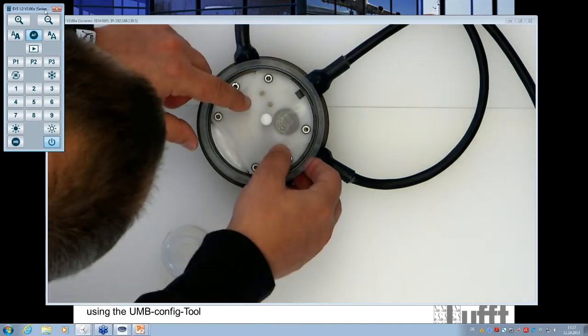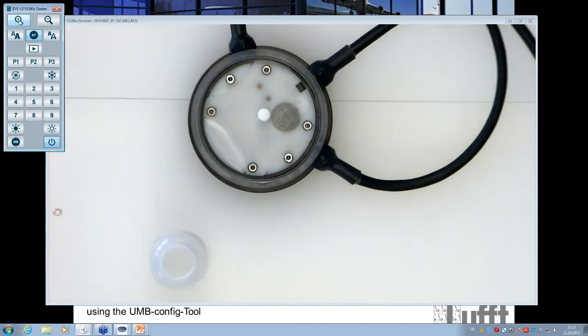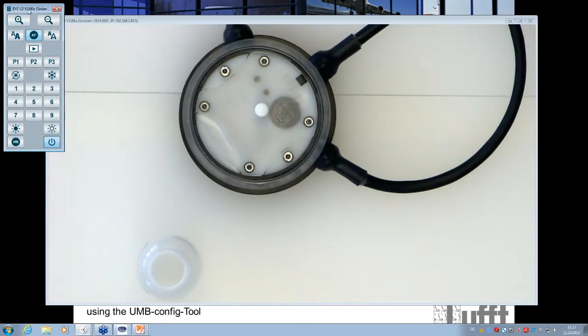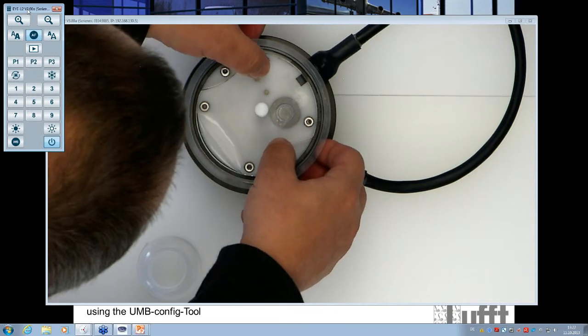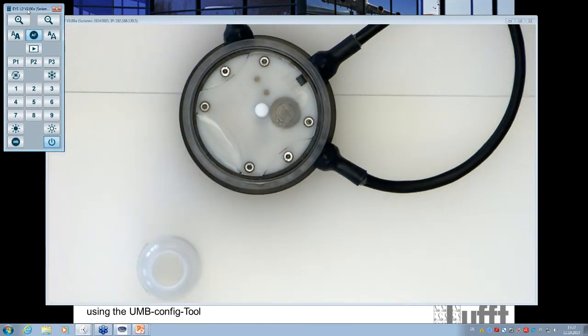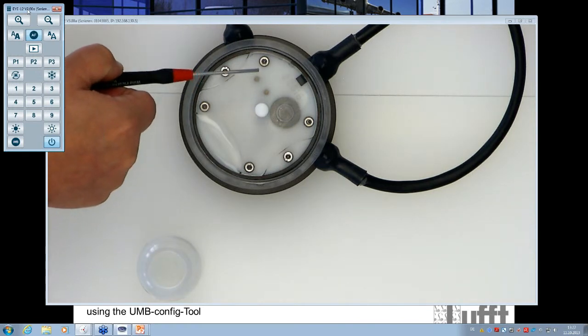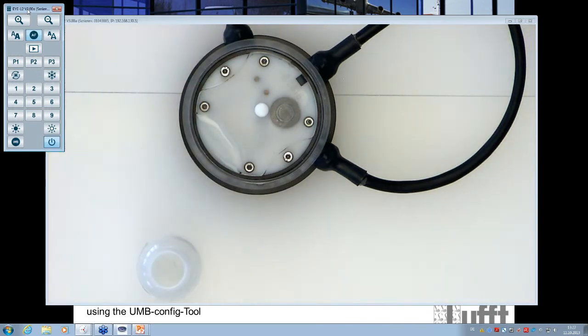and put it on the sensor. Check that there are no bubbles under the insert. So you have to check that there are no bubbles. Bubbles will influence the measurement, especially here where you have the two electrodes. There should be no bubbles there. And then you can start the measurement.